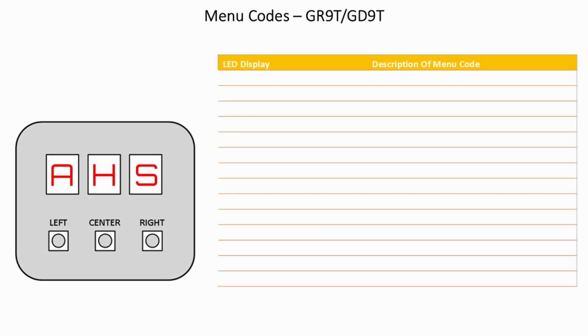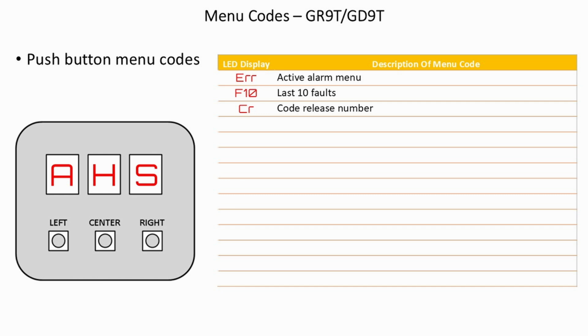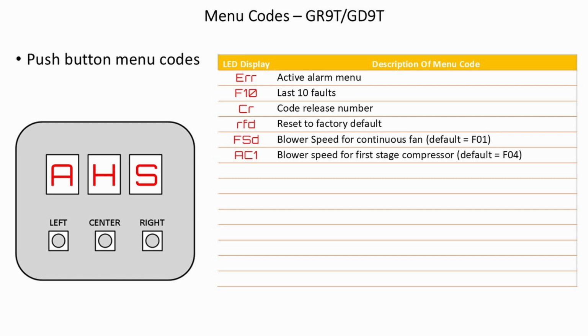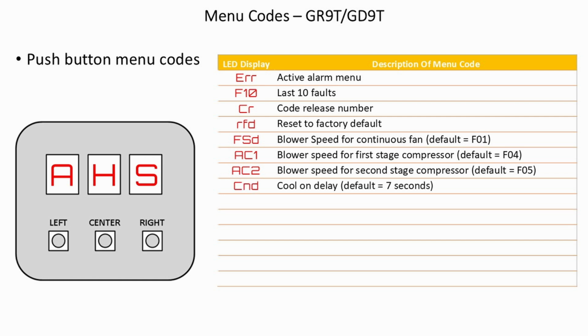Menu codes, GR9T, GD9T. Push button menu codes. ERR, active alarm menu. F10, last 10 faults. CR, code release number. RFD, reset to factory default. FSD, blower speed for continuous fan, default F01. AC1, blower speed for first stage compressor, default F04. AC2, blower speed for second stage compressor, default F05. CND, cooling on delay, default 7 seconds. CFD, cool off delay, default 65 seconds.